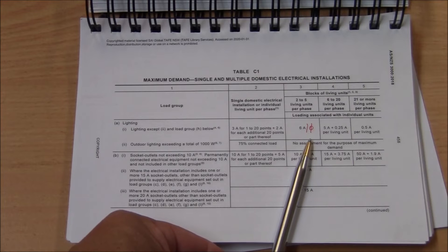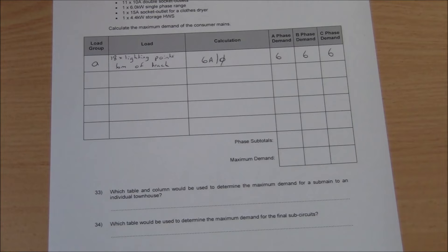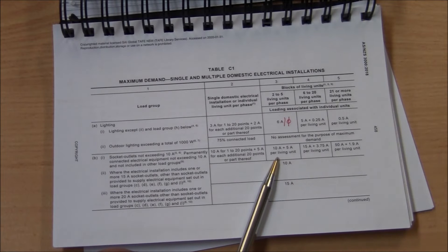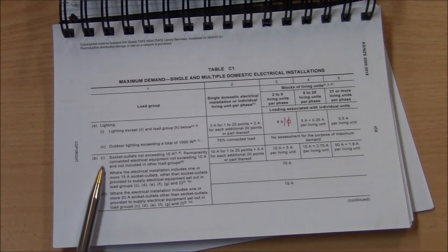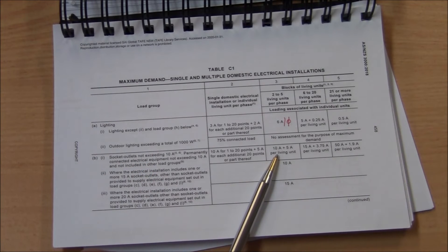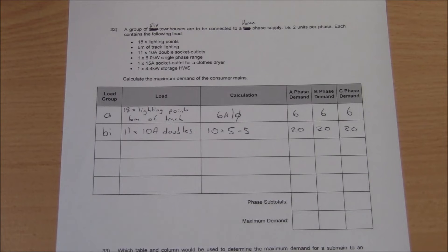Next is 10 amp socket outlets. Each unit has 11 double 10 amp outlets. Once again, column 3 of load group B, socket outlets not exceeding 10 amps, indicates a 10 amp initial contribution plus 5 amps per living unit per phase. In this example with two units per phase, we would be adding 20 amps per phase.